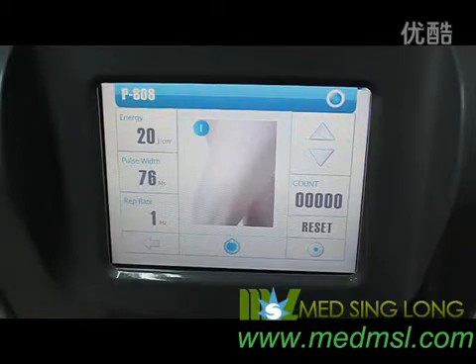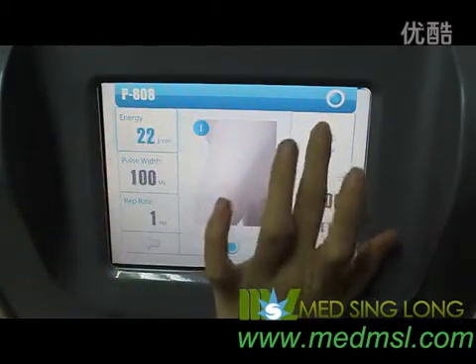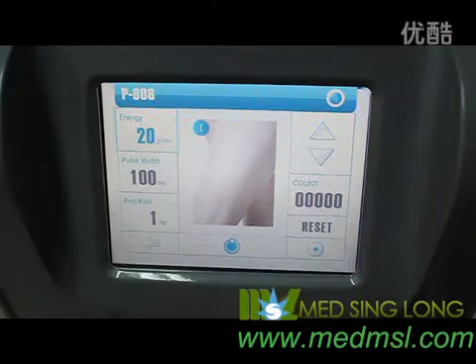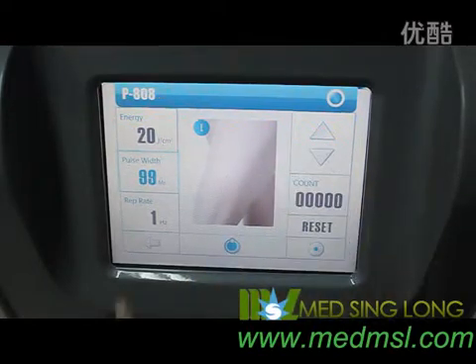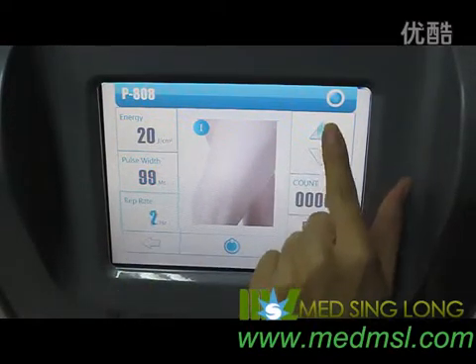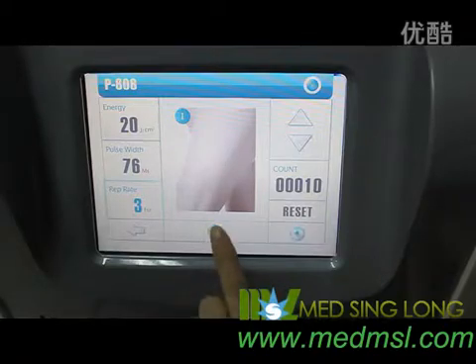We have shown how to use the default setting. You also could select all desired parameters as follows. Touch the energy, then touch up and down on the arrow soft key to adjust it. Touch the pulse width, then touch up and down to adjust it. Touch the repetition rate, then touch up and down to adjust it. Note: this is in ready mode and the operating parameters cannot be changed. To change parameters, turn to standby mode.